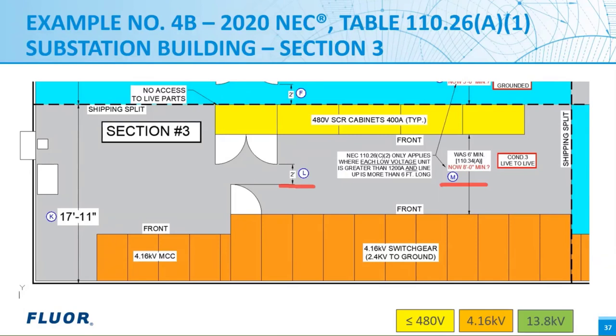This possibly creates another issue for us, even though it's not electrical. Bubble K off to the left-hand side indicates nearly 18 feet now for section three. Depending on where this building section is going to be shipped, if it's within the United States over roadways, it may be too large to put on a truck. That would mean we'd possibly have to rearrange the location of the shipping splits or add more of them. Possibly another thing we could do is rearrange the entire substation so the shipping splits land in the correct location.